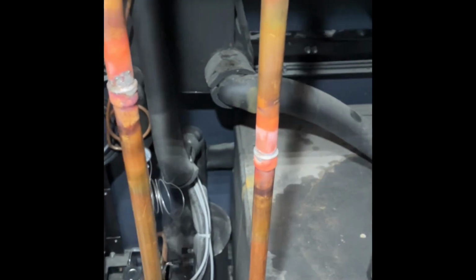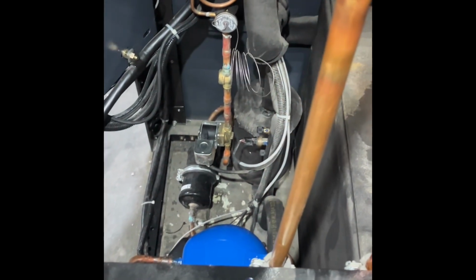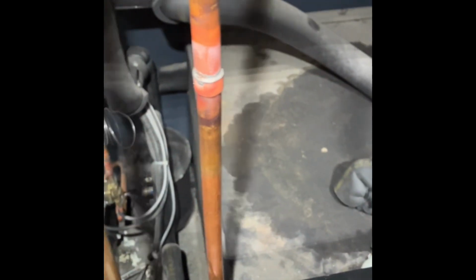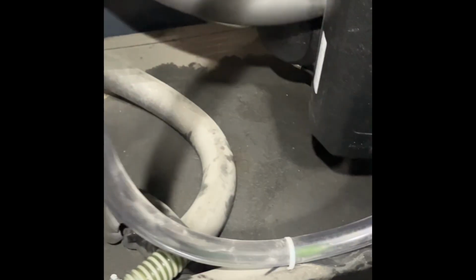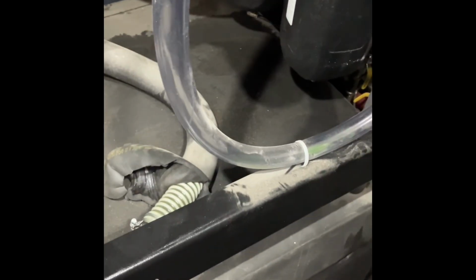So what we're looking at right now is we have a near complete refrigerant loss. According to the controller, I have like 11 pounds of suction pressure right now with the dryer off. So that's one complaint. The other complaint is that the client says he's been seeing green liquid on the floor underneath this thing. So kind of signaling to me we have a glycol leak somewhere.